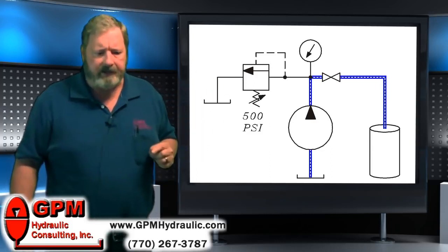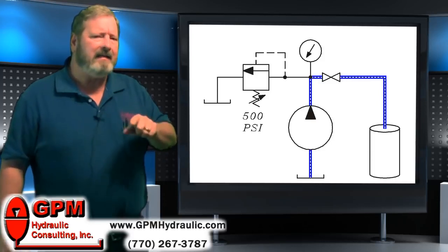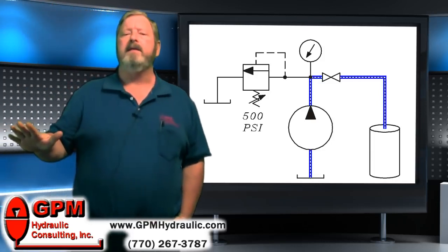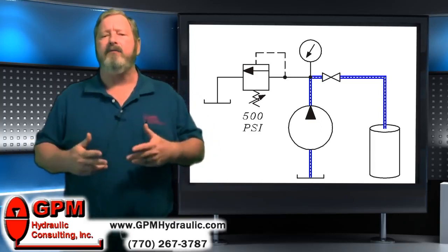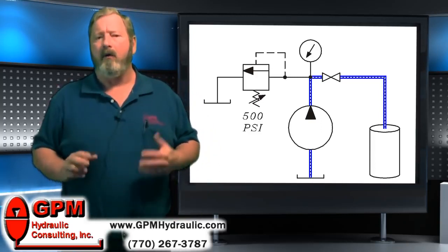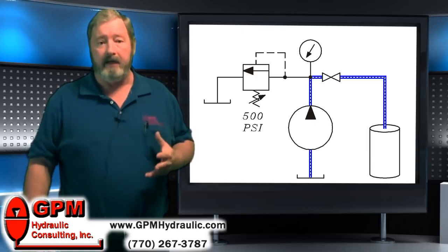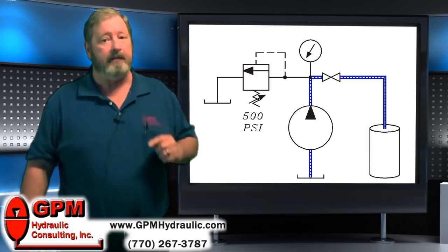But let me ask you a question. How many times have you seen a pump changed for no other reason than because the gauge read 0 or lower than someone thought it should be? Personally, I've seen it hundreds of times, and it's typically a mistake.